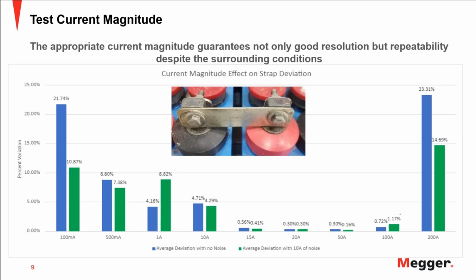Just to give an example of how the current magnitude affects the measurement, this is not exactly a bonding application, but it's a connection of two terminals in a battery. We want to measure the resistance of this contact plus the resistance of this contact here for the strap. One side of the instrument touches the post, and the other side touches the other post, to measure this contact resistance plus the conductor plus this other contact. So we perform the test with different currents, and with each current we perform the test multiple times.